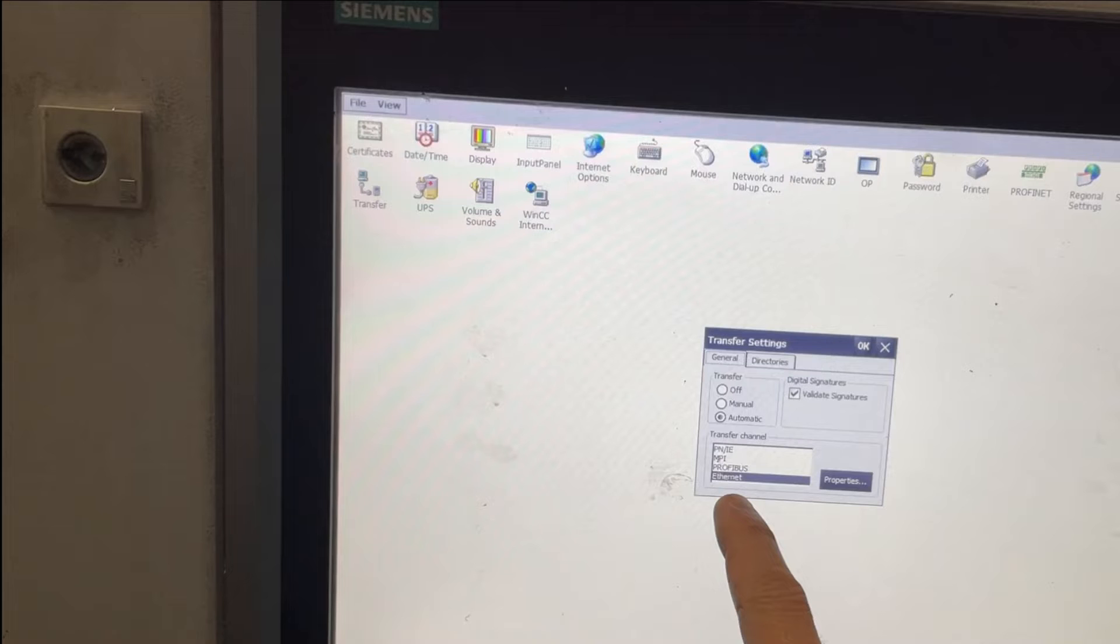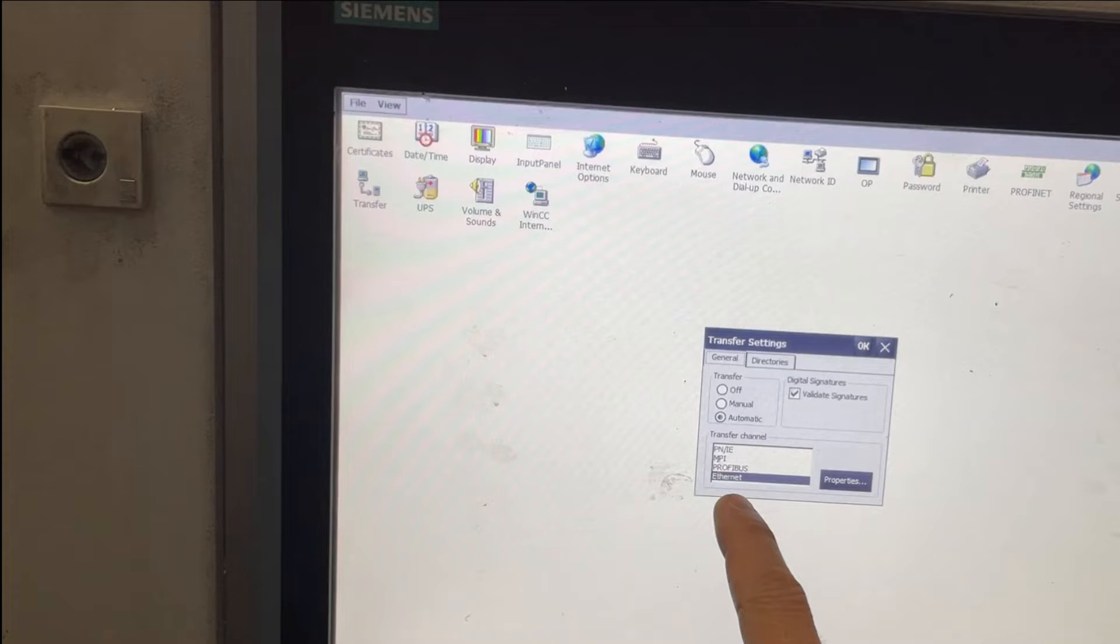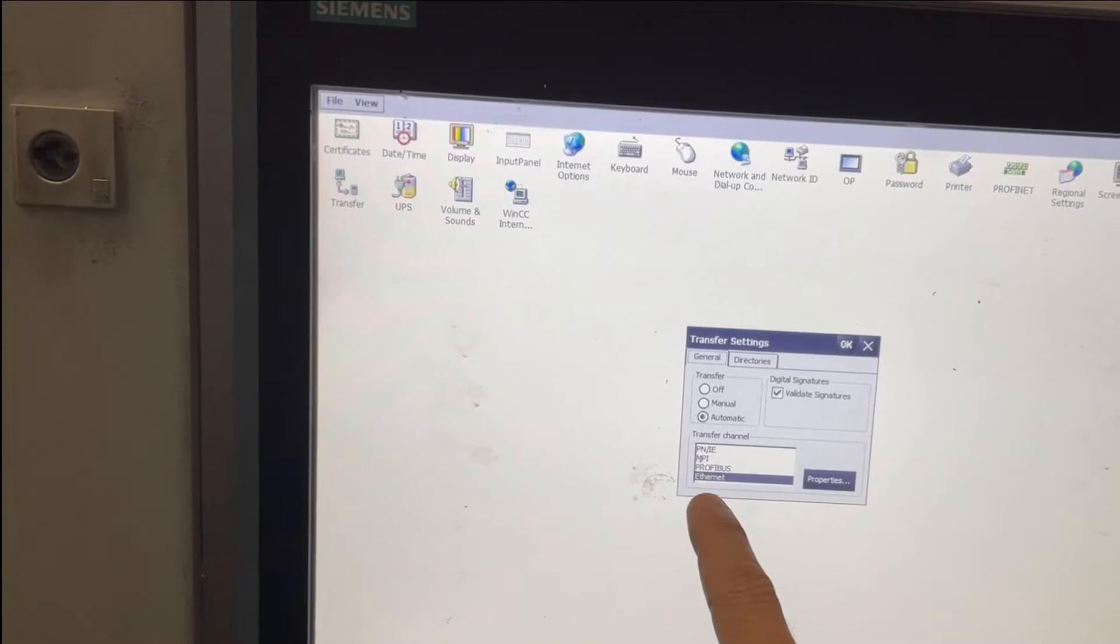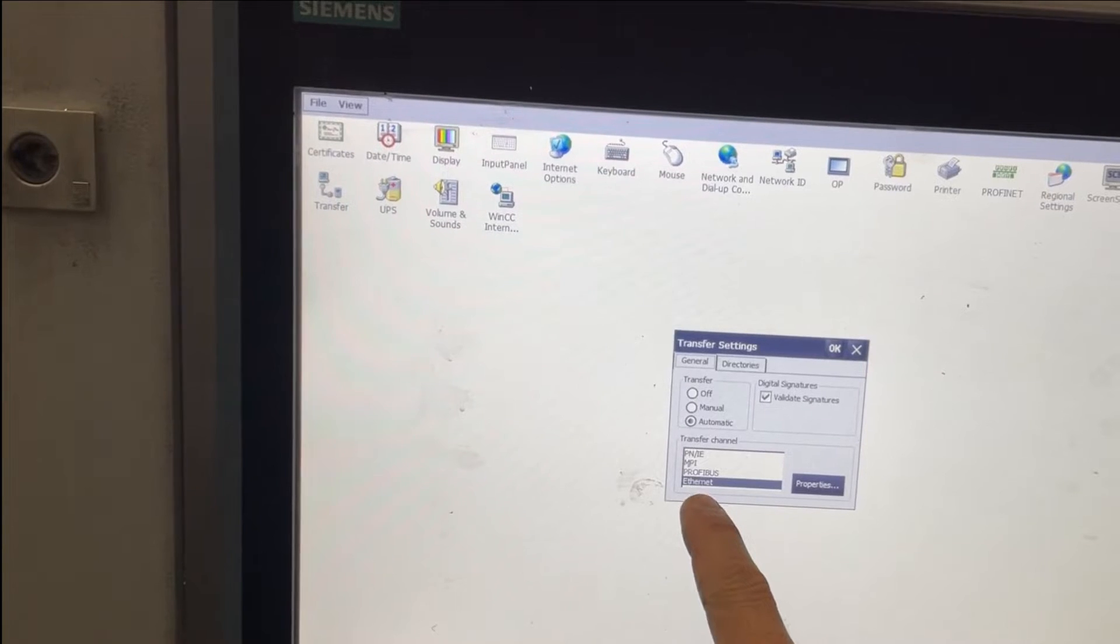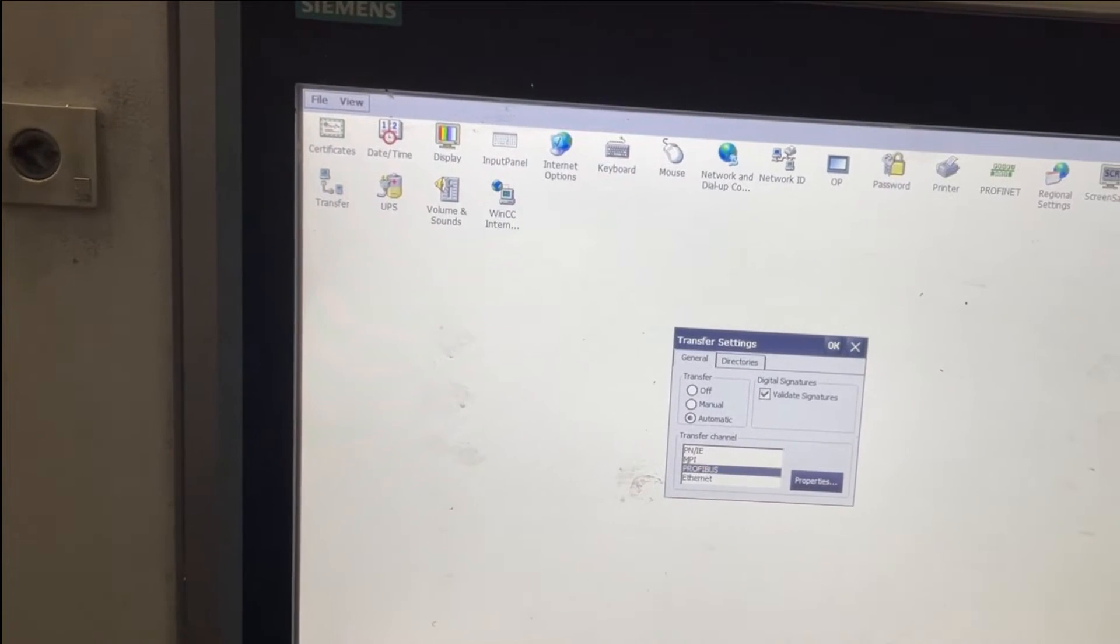The funny thing here is even if I choose Profibus, it still will work as Profinet. I should choose the PN IE, but even if I chose Profibus, it still will work, which I'm going to show in this example.